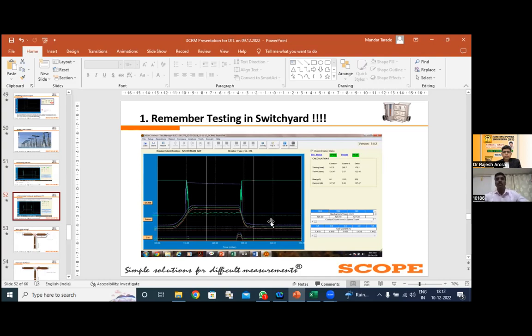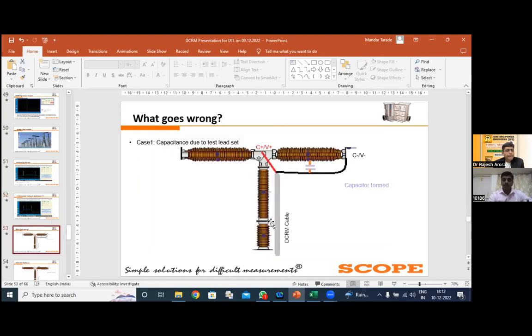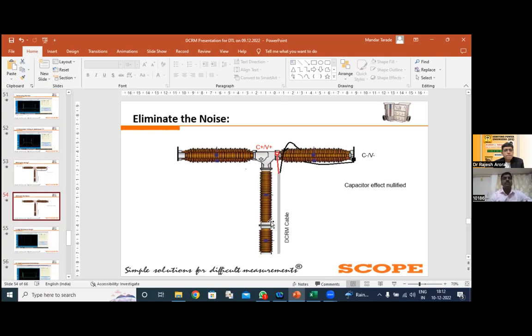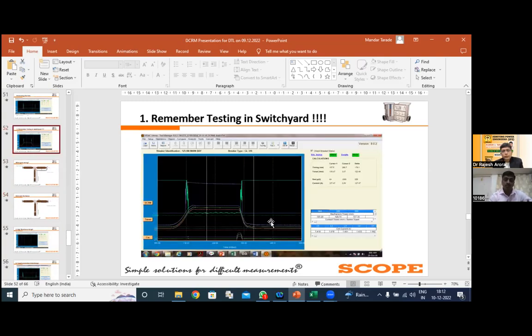or we need to wrap the cable around the interrupter. Why? Because we are preparing a low pass filter. If the low frequency, that is the 50 Hertz signal, is coming, then with the help of just a simple one wrap, we can eliminate that noise, because from the height of 14 meter or 12 meter, we are bringing that signal to ground. So it is possible that the 50 Hertz noise will get coupled. But we don't want the 50 Hertz coupling noise. We want the signature as smooth as possible.